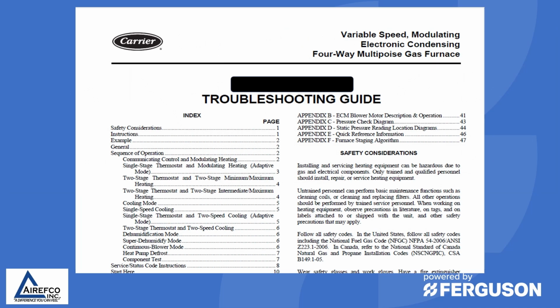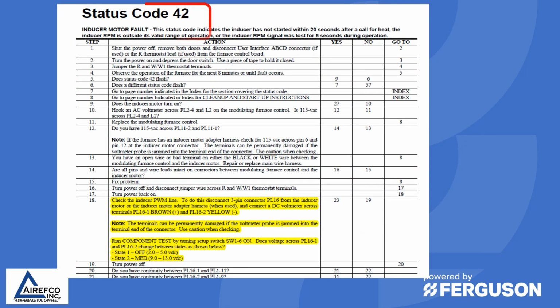In order to correctly troubleshoot these ECM motors, you have to have the troubleshooting guide that gives you the voltages that you're supposed to see on the communication line. These troubleshooting guides are readily available on the Carrier TechLit app and the Bryant TechLit app. So in these troubleshooting guides, you have the various status codes, fault codes that will be shown on the thermostat or flashing on the furnace control board.